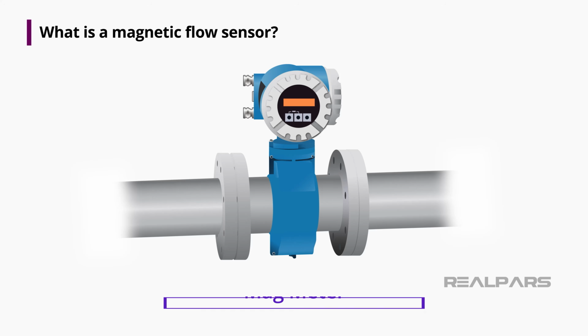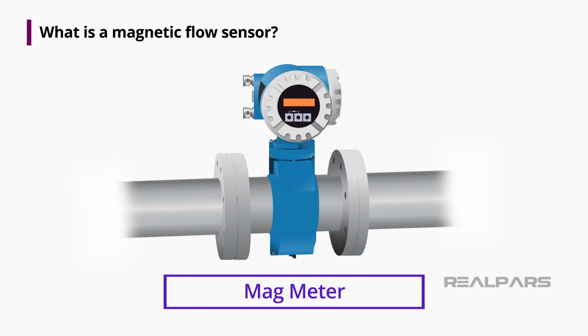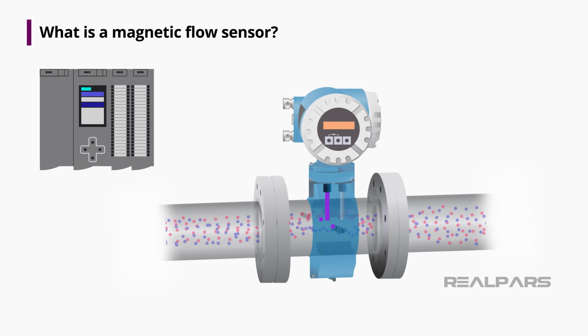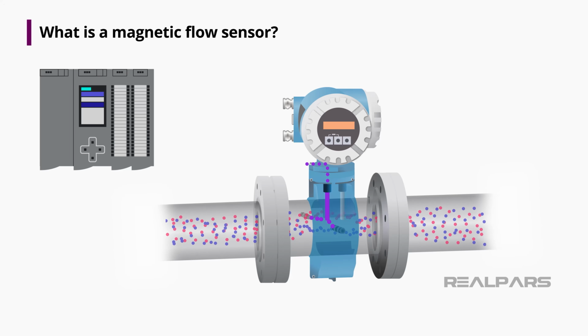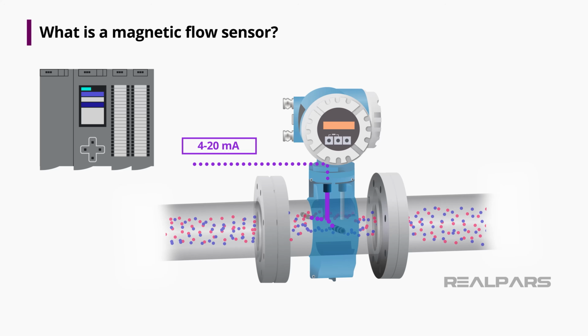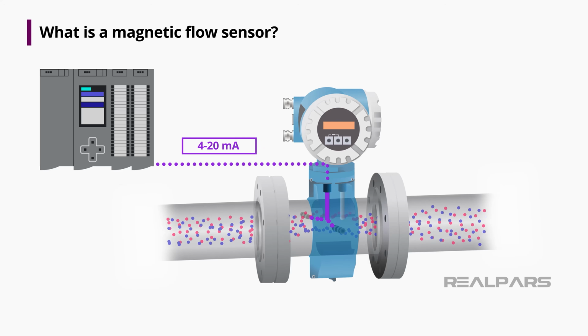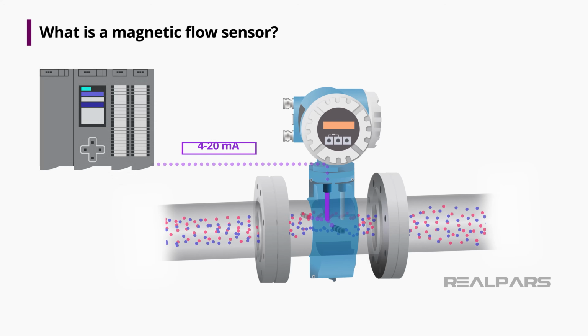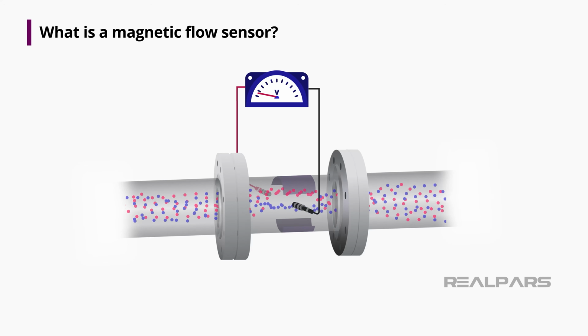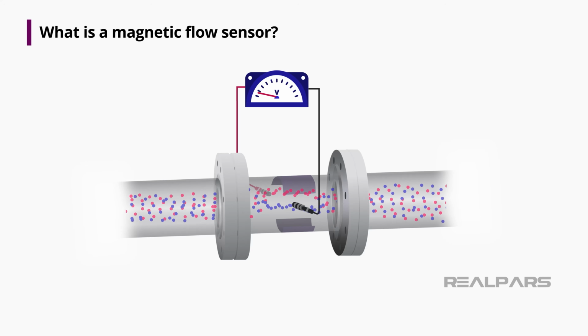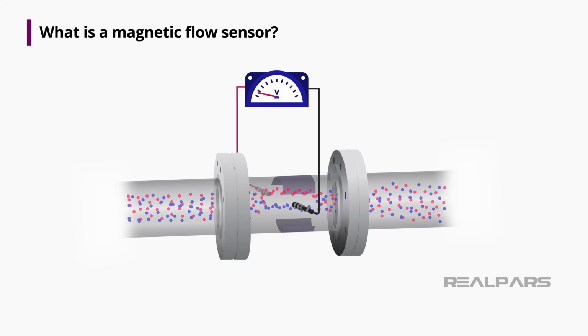Magnetic flow sensors are often called mag meters, and I will refer to them using this abbreviation. Let's look at the physical properties of how a magnetic flow meter converts velocity into a flow signal that can be used in a control system. Previously, I mentioned that mag meters convert a velocity into a measurable electrical signal. How does this happen?